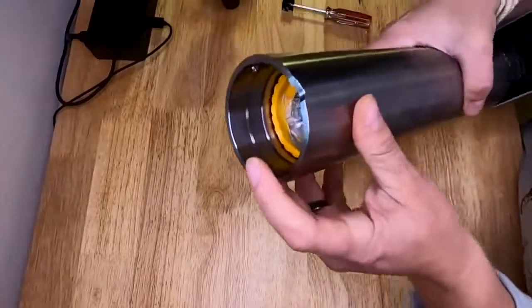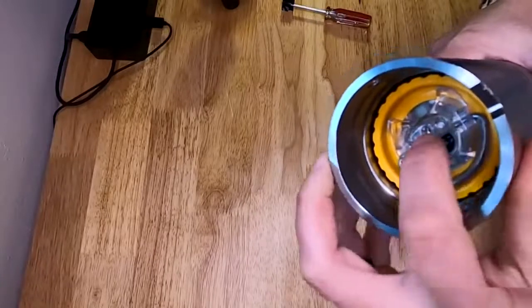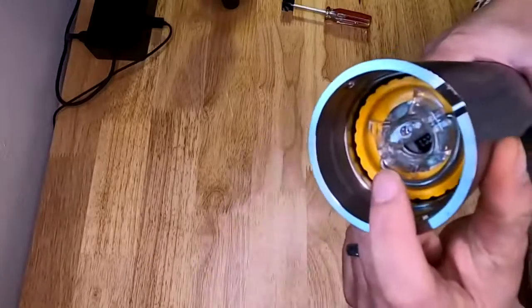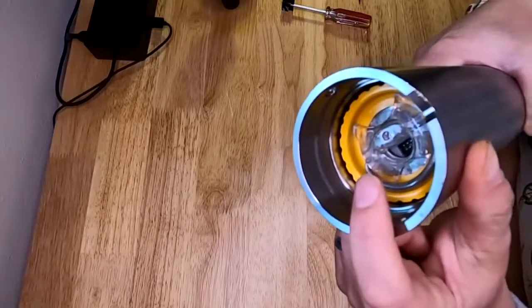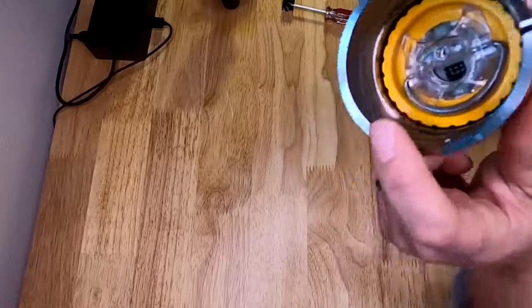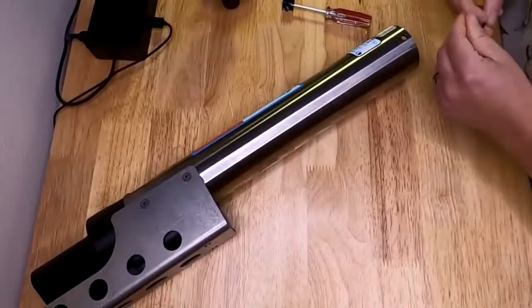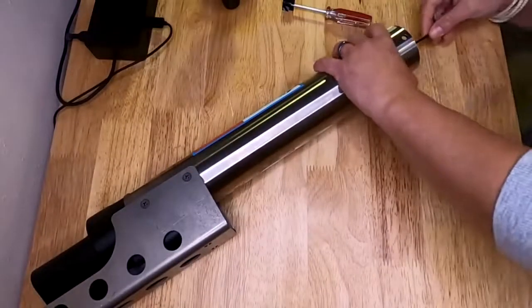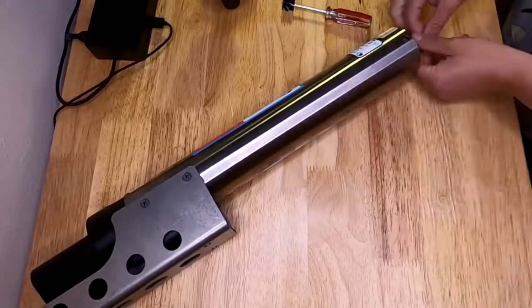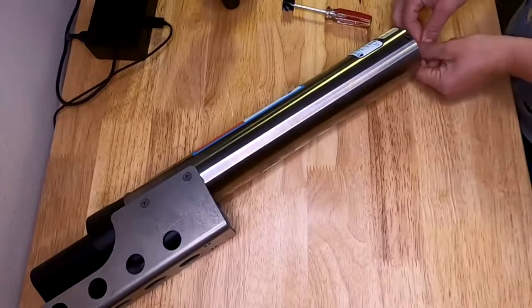All right, so once you open it up, that's where you get into your battery pack. So that's here. You can see it right here in the middle. You can't just pull this battery cap out. It's connected by a small captive screw that actually keeps it in there. This is to prevent the batteries from rolling around. If you know anything about moorings, they undergo a lot of dynamic changes when they're in the ocean. So this thing will get bumped around a lot, and so you want to keep everything in place.